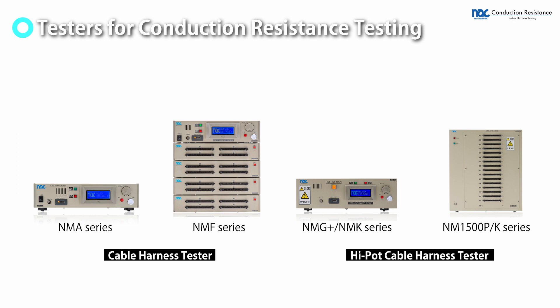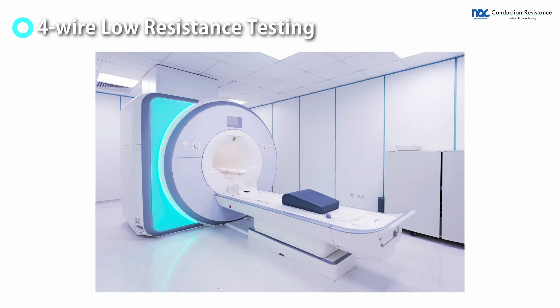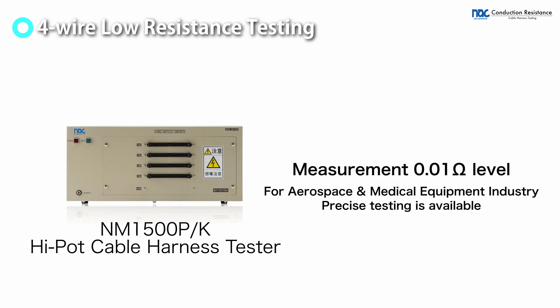Conduction resistance testing can be performed with cable harness testers and hi-pot cable harness testers. In the aerospace and medical equipment industries, conduction resistance testing at the 0.01 ohm level is especially required.